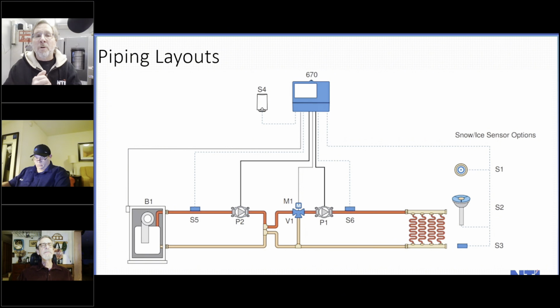And on this, it has a motorized 3-way valve that the controls also handle besides the pumps on either side. This 670 is capable of slowing up or speeding up your boilers on either side, so it can protect the boiler and protect the snowmelt from heating up or cooling down too quickly.